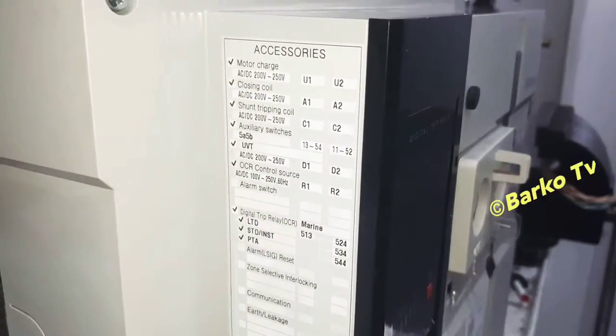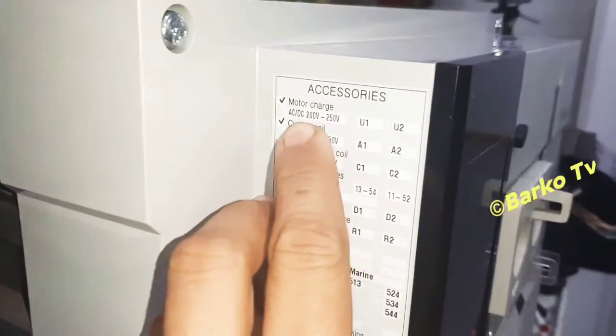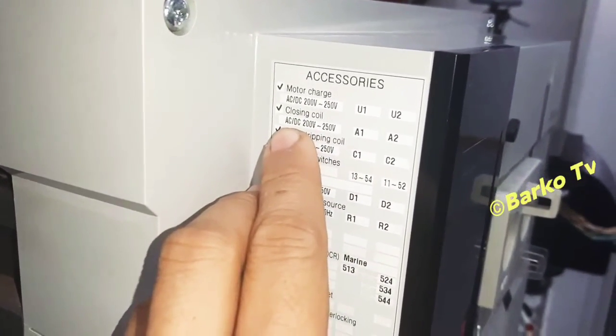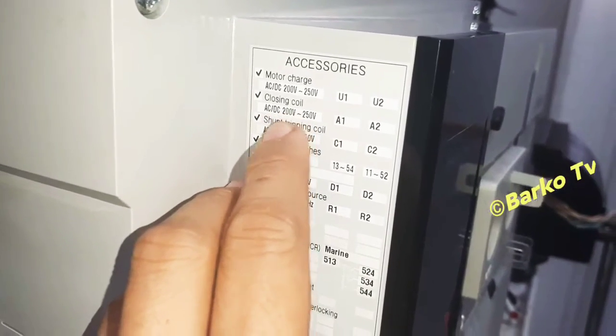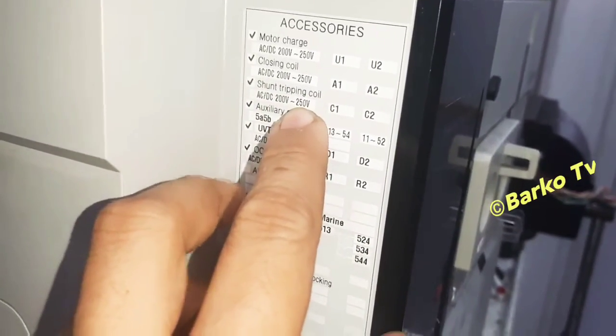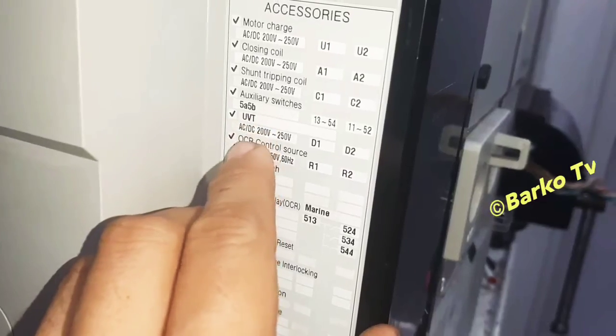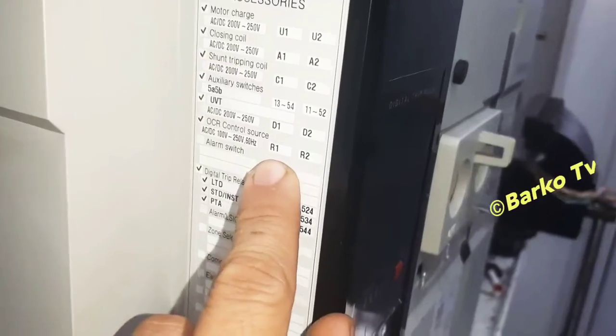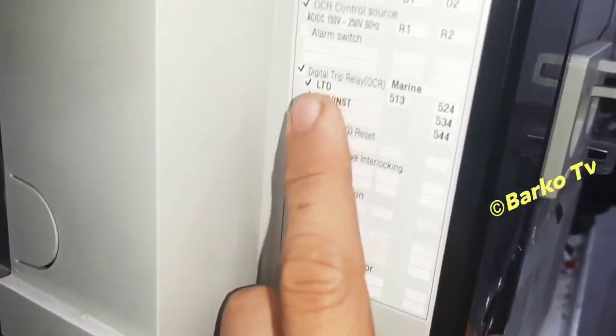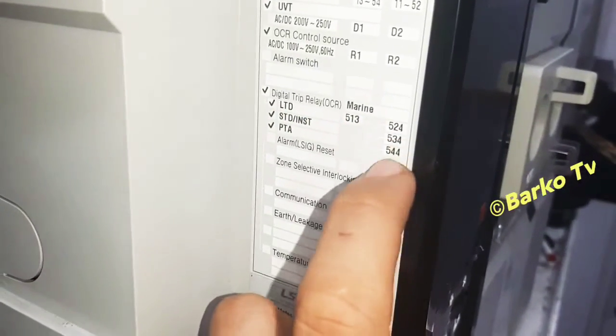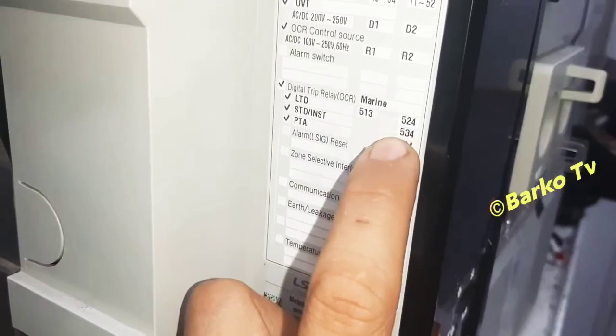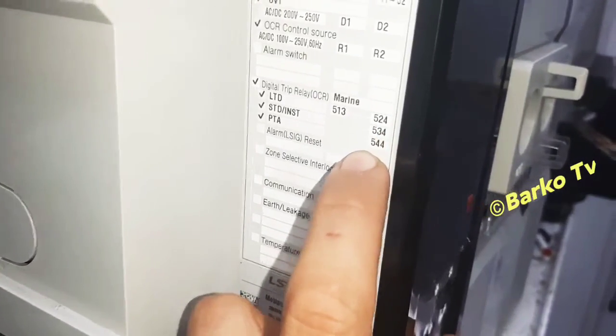This is the nameplate and accessories. Motor charge means the motor supply is 220V. Closing coil is 220V, shunt trip coil is 220V, auxiliary switches and UVT is 220V, OCR is also 220V. This is the digital trip — it has long delay, instantaneous, short, and pre-trip alarm.